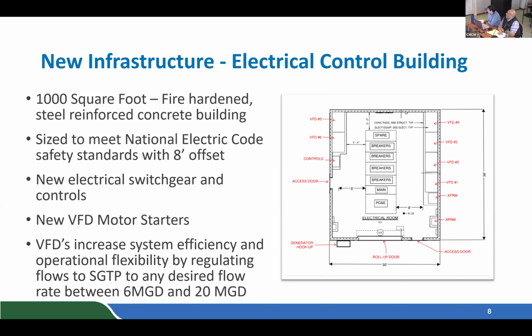So this is a schematic of what the new building is going to look like. It increased in size to 1,000 square feet. It'll be a fire hardened, steel reinforced concrete building, so it'll have a metal roof and concrete masonry unit walls. It's sized to meet modern National Electric Code safety standards with the 8-foot offset, which is the main reason why it grew in size. That and the VFD drives are actually physically larger than the traditional direct across the line starters. So this 8 feet right here really drove the width of the building.